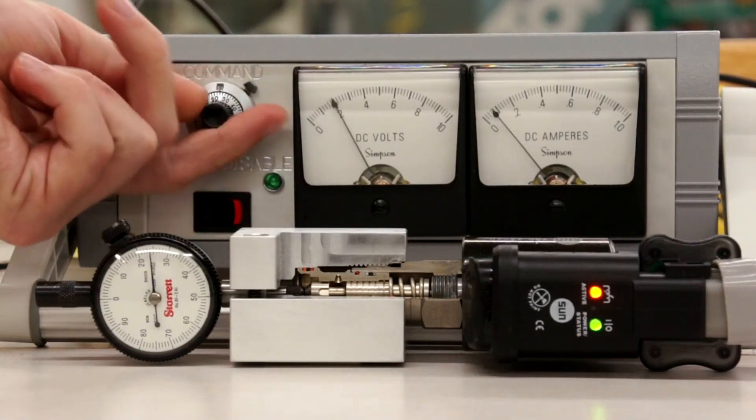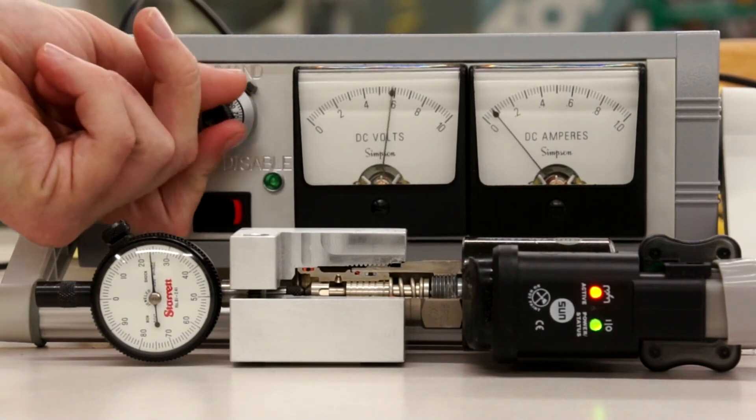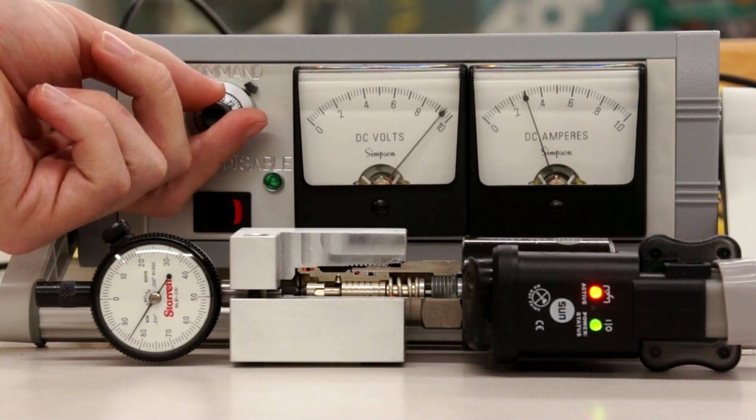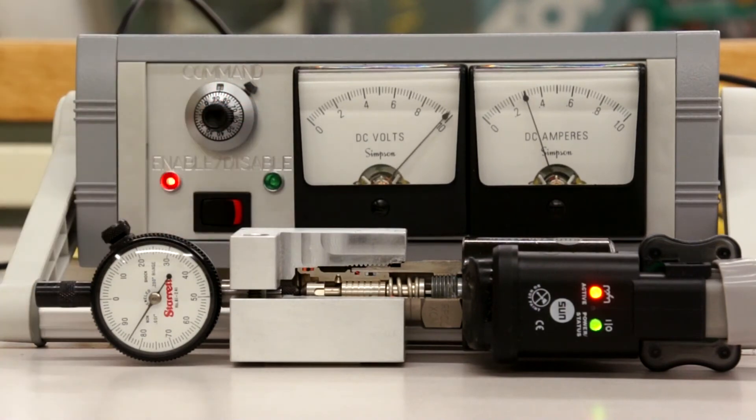The other input is full command, and when we say full command, we mean anything between 8 and 10 volts. So now that we have crossed the threshold of 8 volts, we are fully stroking the valve.